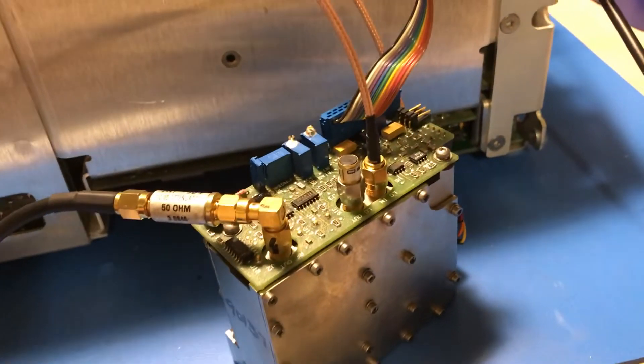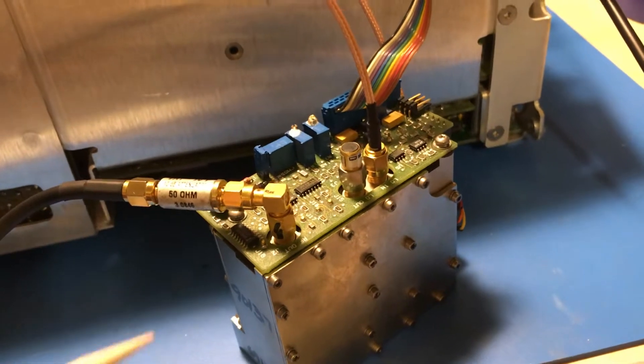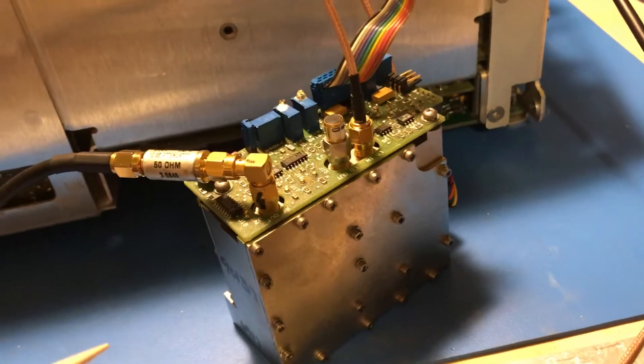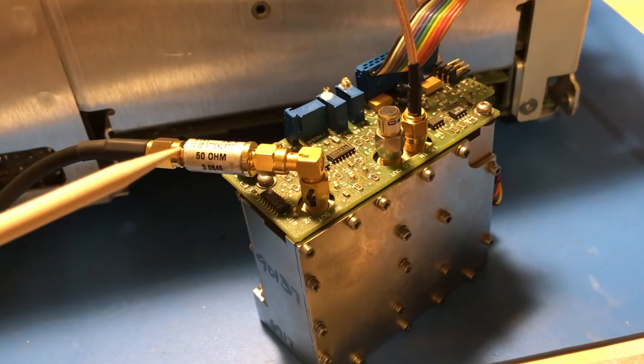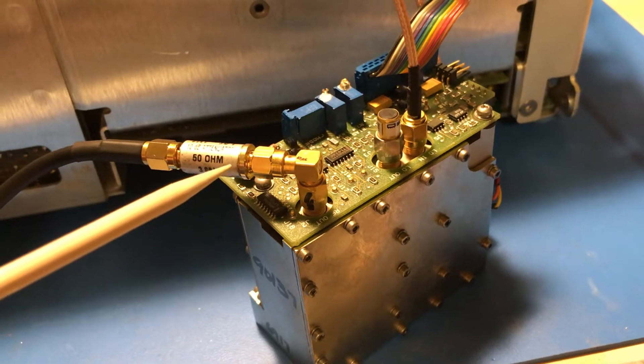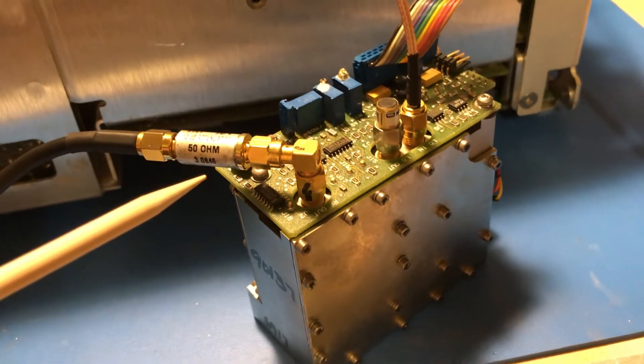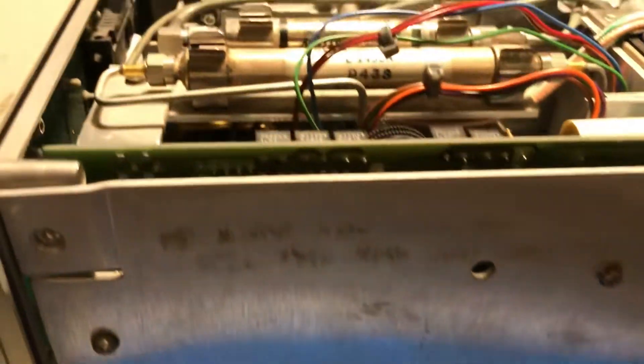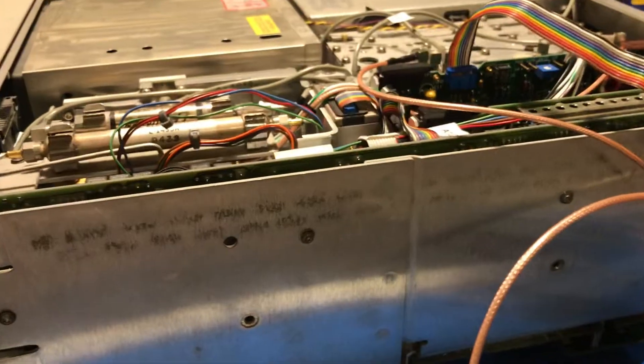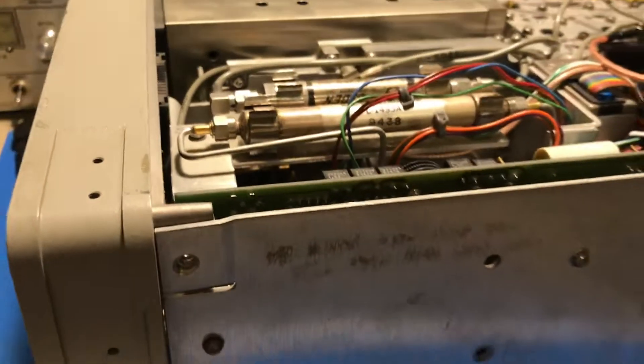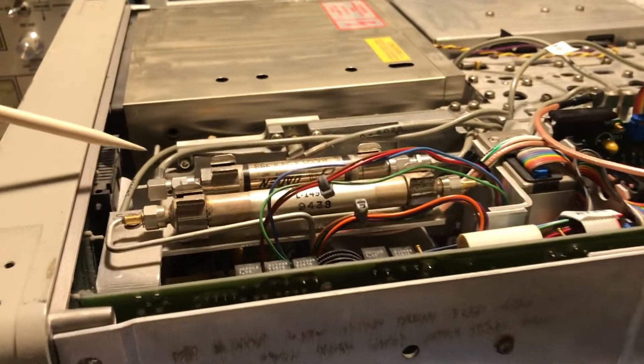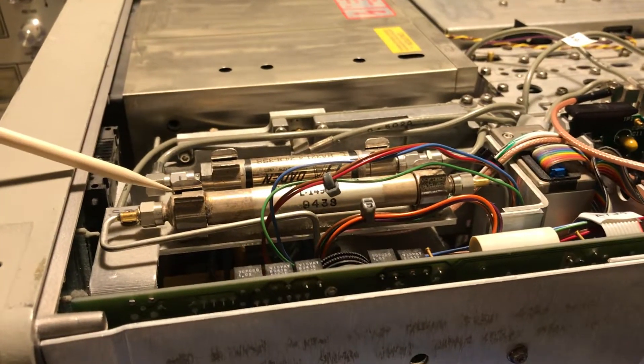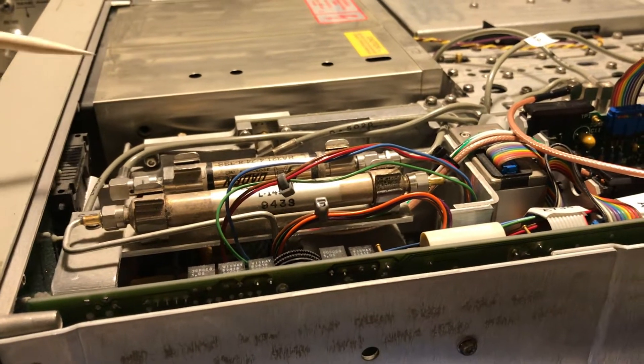And of course the tracking generator itself. Still waiting on the last part to arrive, which is a step attenuator off the output. For the upgrade, first thing you got to do is take the unit apart, take off the front panel. You've got to bring the RF front end completely out of the unit.